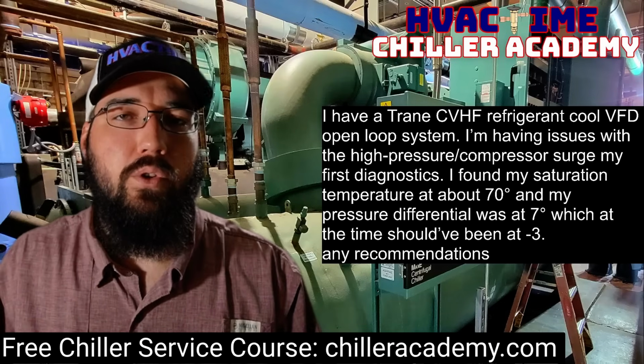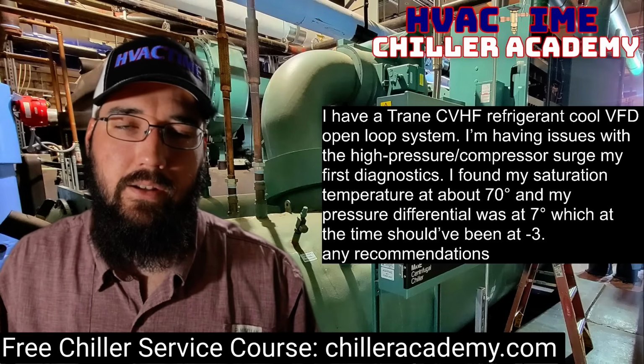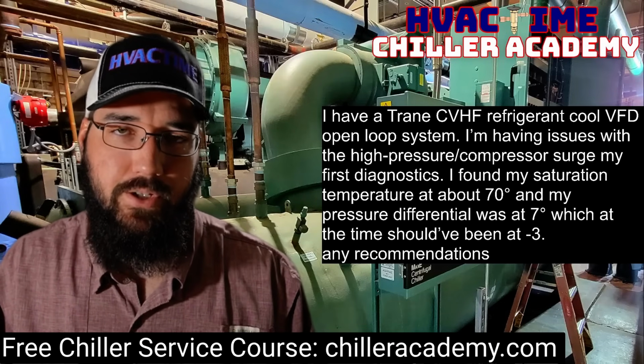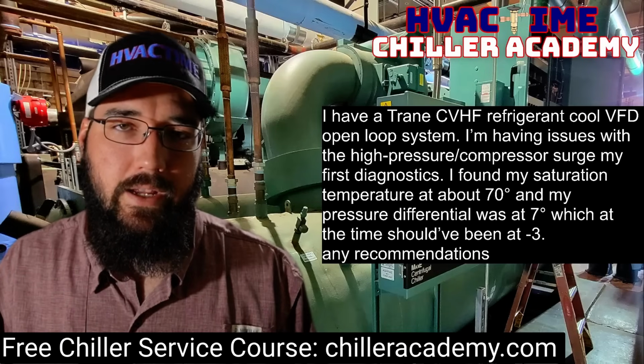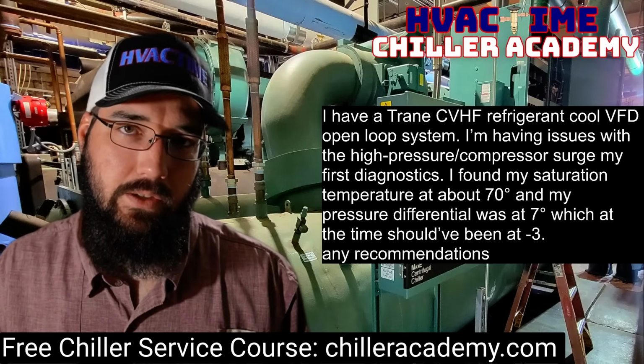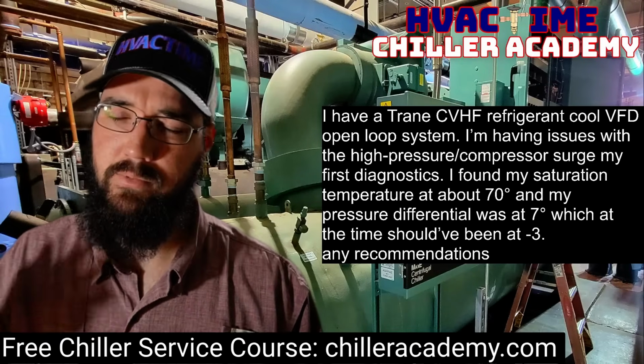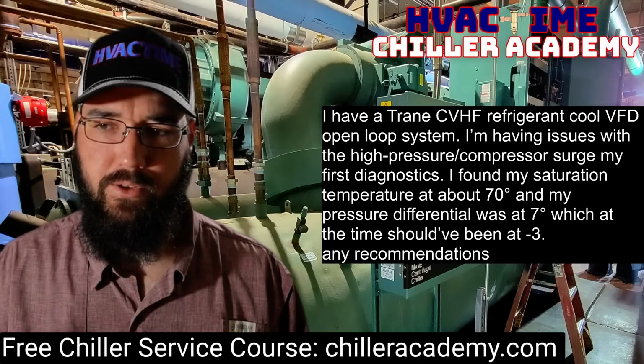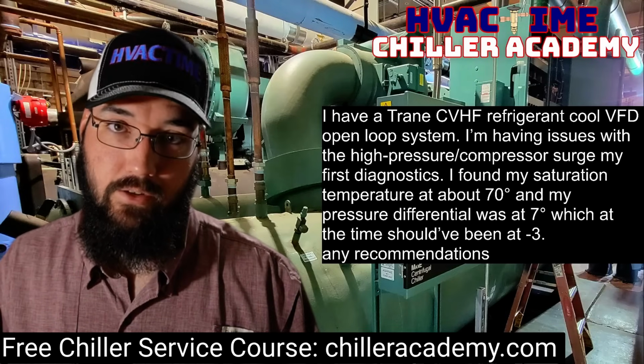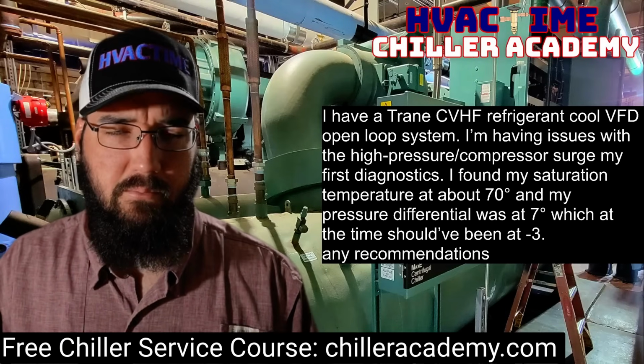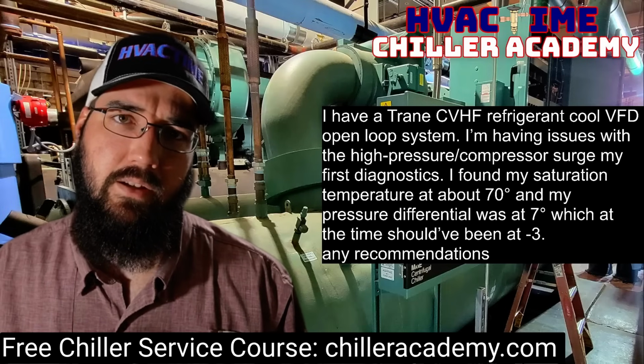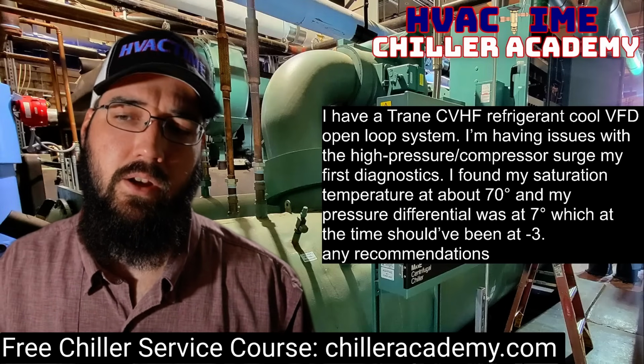So yeah, once you get to where you can start up, that's great. It's good to get the machine running. I really care about why this was necessary in the first place. Is it a purge unit problem for the chiller itself? What kind of leak are we dealing with in the first place? I care more about the DP than what the VFD speed is on my pump.